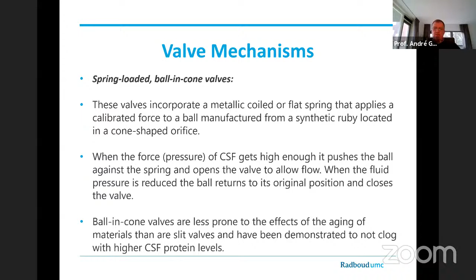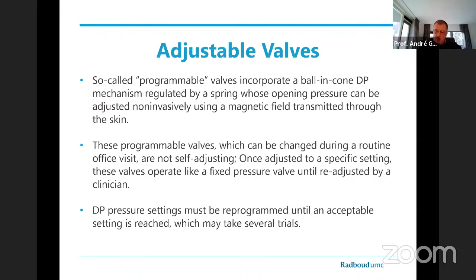Well, and then of course we have these programmable valves. We call them programmable, but I would say adjustable is better, because they are of course not self-adjusting. The only thing is, when the child or the patient comes into your office with a magnet, you can change one pressure setting to another. The moment you have changed it, it is again a fixed differential pressure valve, until you readjust it to another value. But the moment you stop adjusting it, it is a fixed pressure. It cannot adjust itself, not at all. And therefore, in some of these cases, you need several readjustments before you really have the desired situation for your patient.